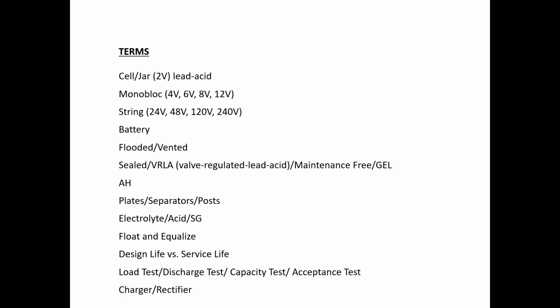Discharge testing, capacity testing, acceptance testing, those are all different terms put out by IEEE. Typically, we just call it load testing. And that's really the best way to determine the health of the battery. I don't have it on this terminology, but ohmic testing with a Midtronics tester or a Megger is the second best way, I'll say, to determine your actual capacity. But a load test, where you bring in a resistive load bank, take that battery offline, and run it down in a controlled way to determine end voltage at a published discharge rate, is really the only way you can determine your actual health of the battery.